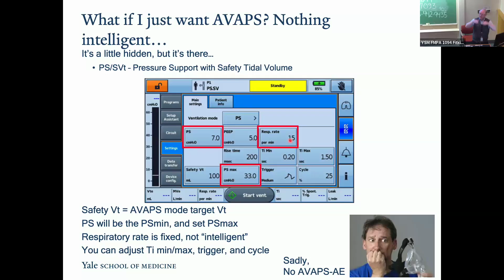So the ResMed summary here: iVAPS, intelligent volume assured pressure support. Remember, it targets alveolar ventilation and you can use the calculator. The intelligent backup rate is not a mandatory rate. If you want an actual mandatory rate, you need to target 2/3 of the number that you put in. So pick a number, multiply it by 1.5. That's the number you actually put into the ResMed iVAPS calculator.